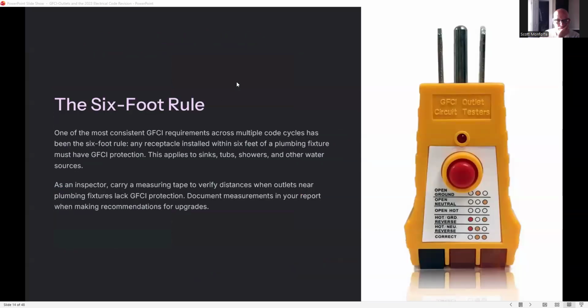6-foot rule. We talked about this just briefly. One of the most consistent GFCI requirements across multiple code cycles has been the 6-foot rule. Any receptacle installed within 6 feet of a plumbing fixture must have GFCI protection. This applies to sinks, tubs, showers, and other water sources. As an inspector, carry a measuring tape to verify distances when outlets near plumbing fixtures lack GFCI protection. Document measurements in your report when making recommendations for upgrades.